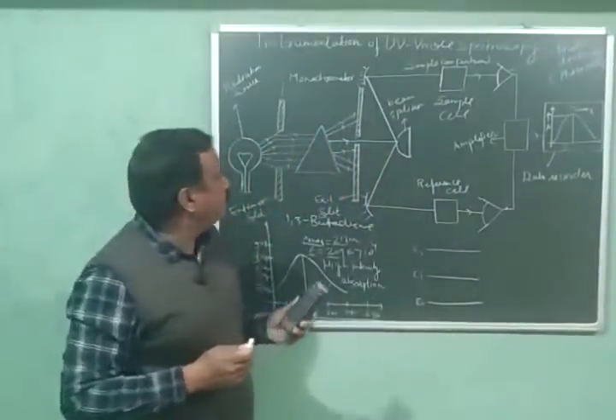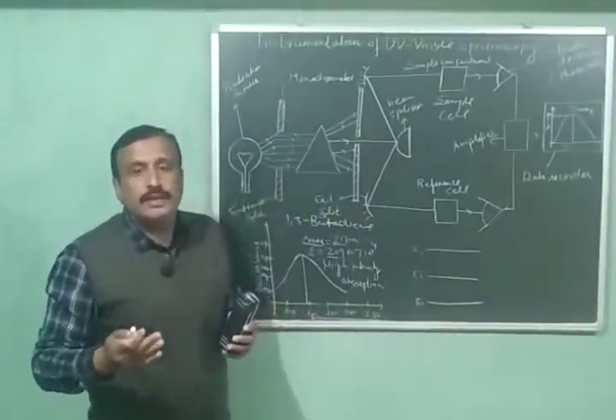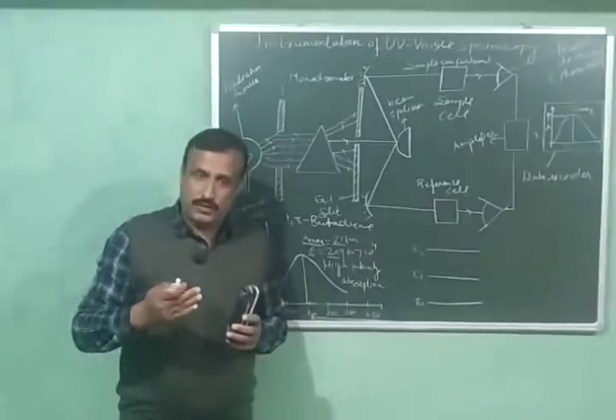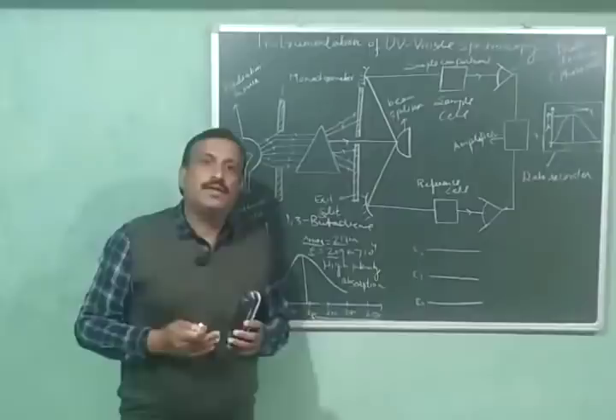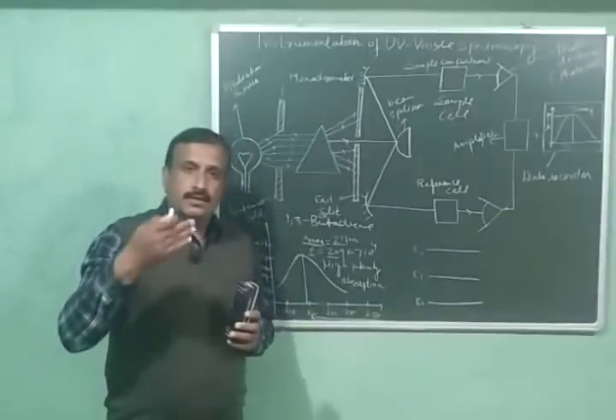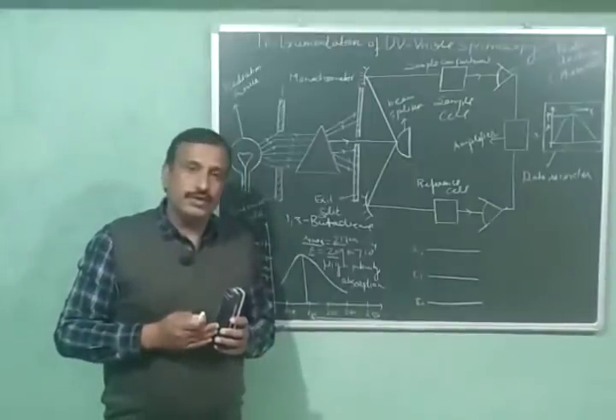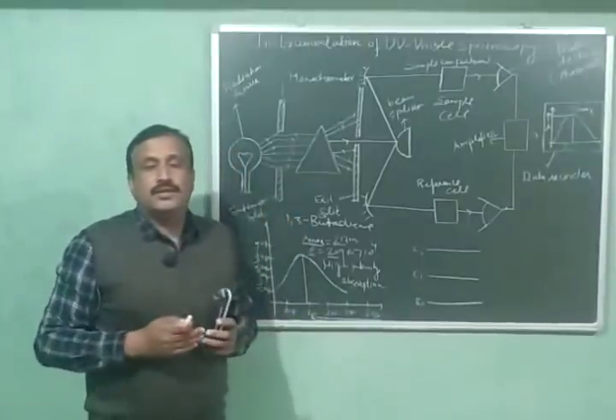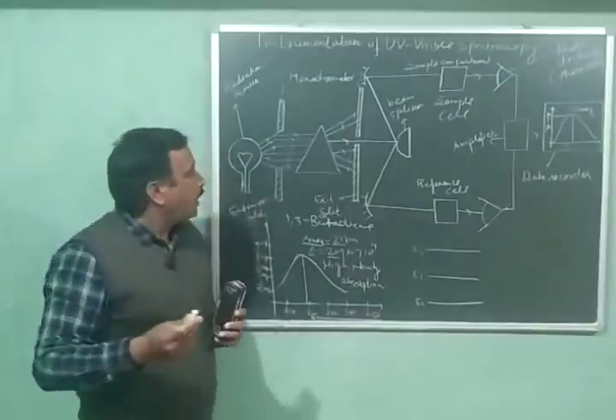The most commonly used radiation sources are the tungsten filament lamp and the hydrogen/deuterium lamp. The tungsten filament is a rich source of visible radiations, whereas the hydrogen/deuterium lamp is a rich source of UV radiations. The radiation source emits radiations of different wavelengths.